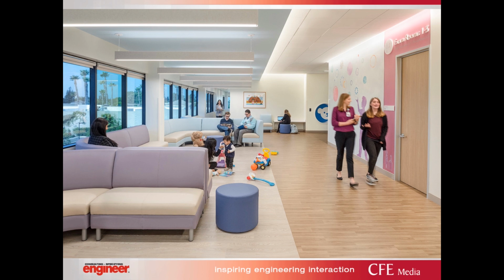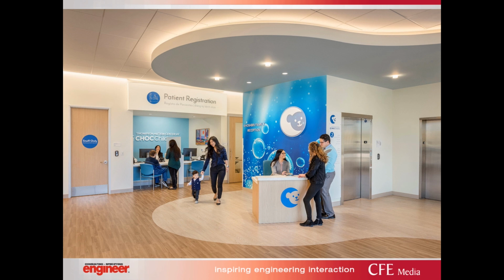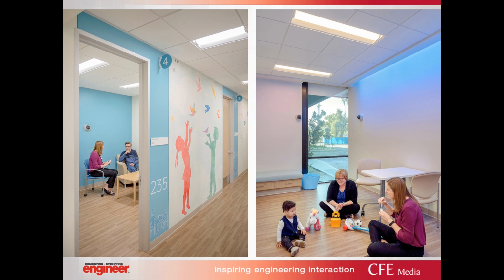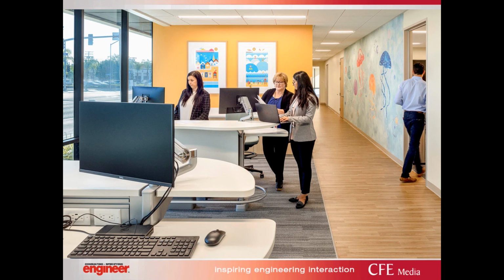As you can see here in the main lobby, all of these fixtures were tied to daylight harvesting since they were along these large window walls. And then in some of the more interior spaces, we were able to use highly efficient fixtures that gave a lot of ambient light and, again, saved that wattage for some of the front of house spaces.